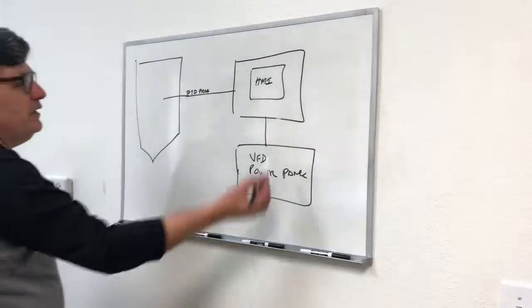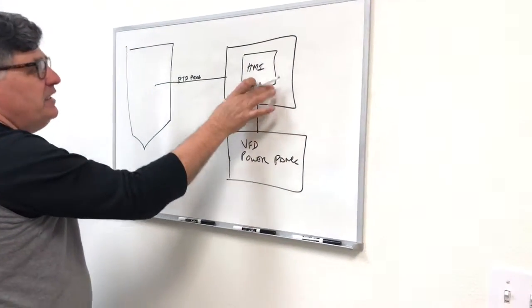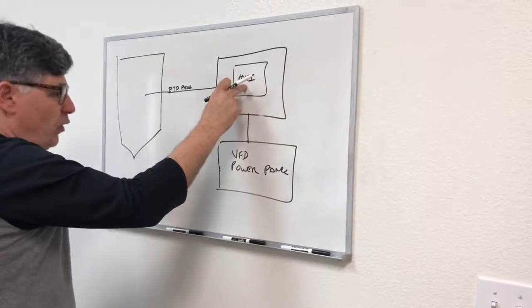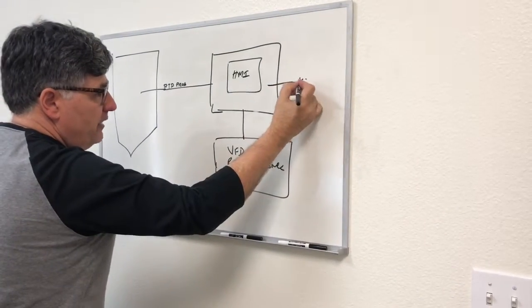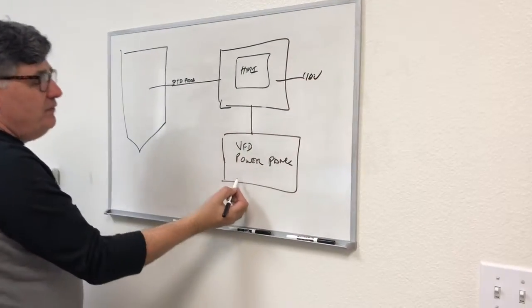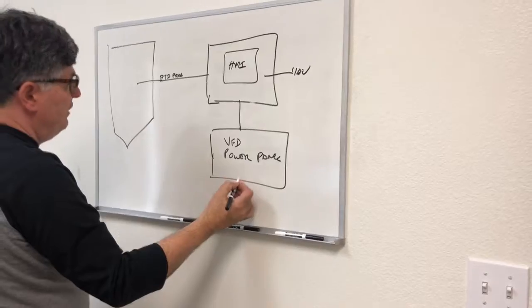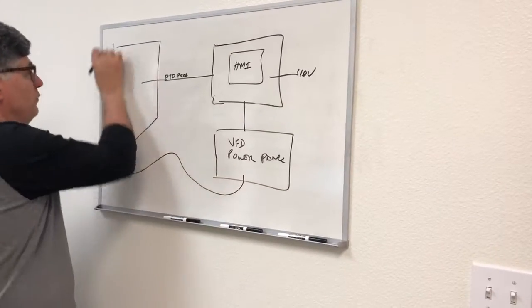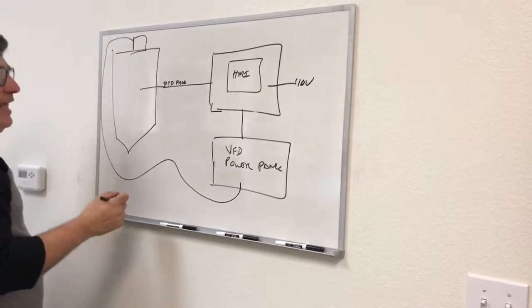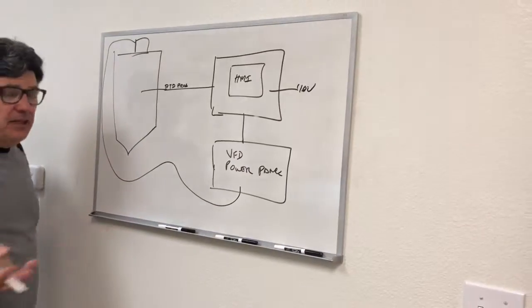Now, even if we have a separate panel that has the PLC and the HMI touch panel on it, and just plug that into 110 volts, and we have a VFD power panel that has the high voltage in it connecting to the motors up to here, we're still going to have the same issue, and this is the same issue that Control Tech is having.